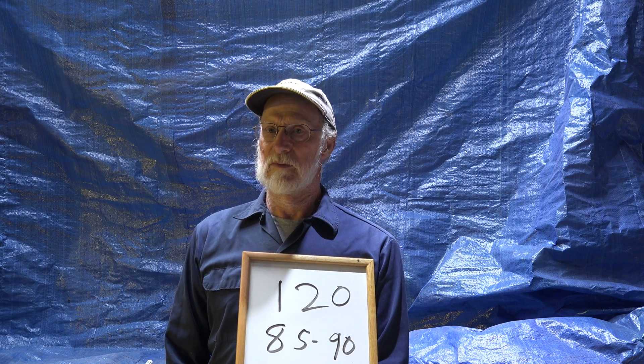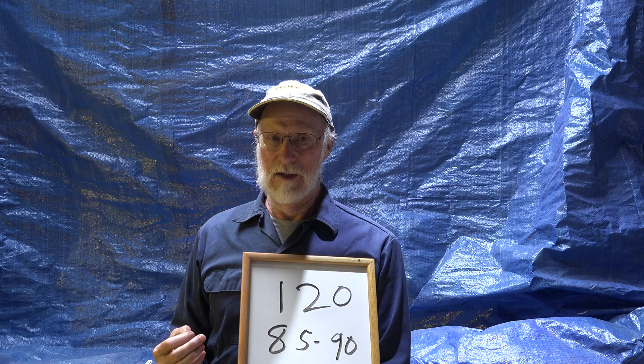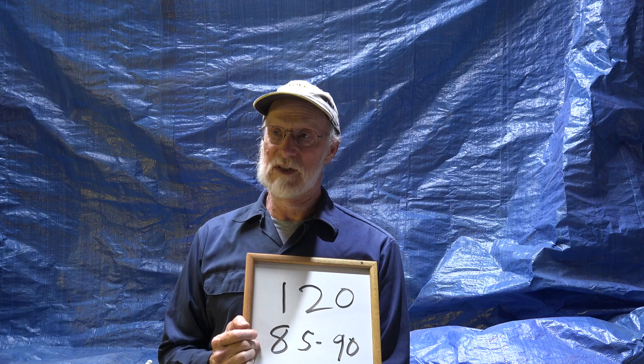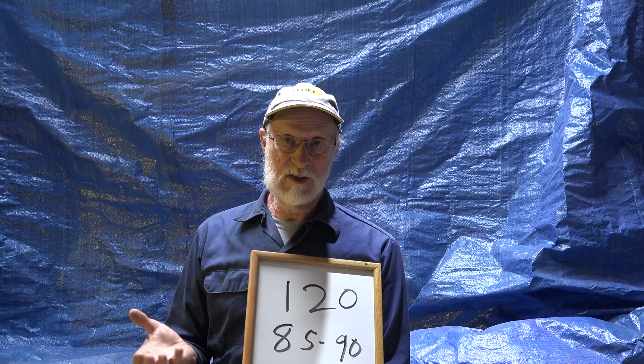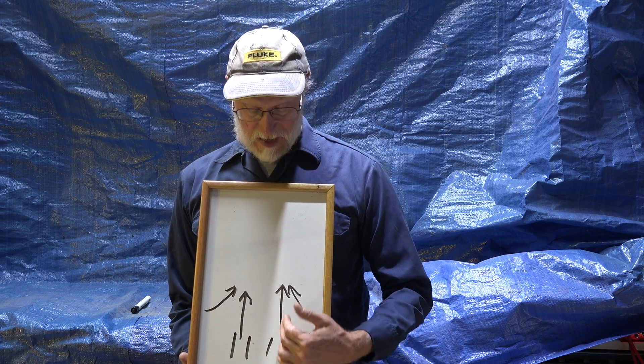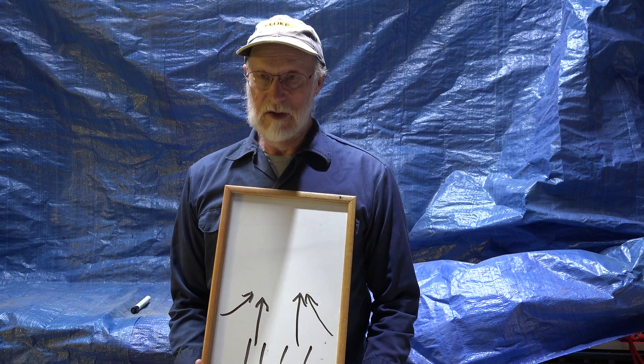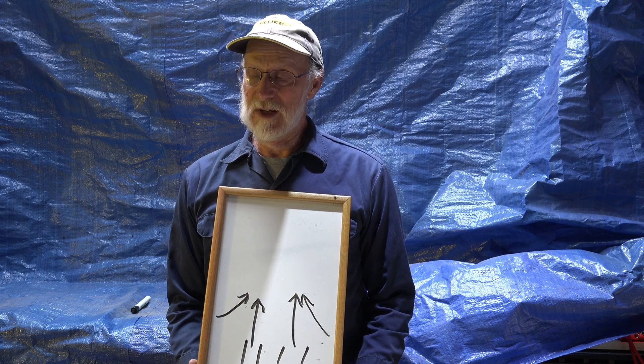In a general sense, 85 to 90 is not going to fly in most homes. But what's good about it is it had virtually no stratification at all — it did not go to the ceiling and stay there, it just mixed with the surrounding air. As your air comes up from a floor diffuser, this is your 120-degree air, and ambient air temperature comes in around it and cools it down. With the heat pump temperature, it barely made it to the ceiling at all.